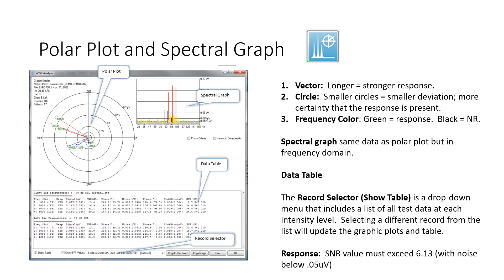And then finally, how do we know if there is a response? Well, the algorithm is, when it analyzes, statistically, the test data, the signal-to-noise ratio has to exceed 6.13 to be considered a response.